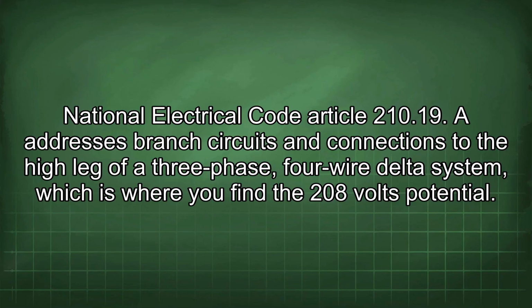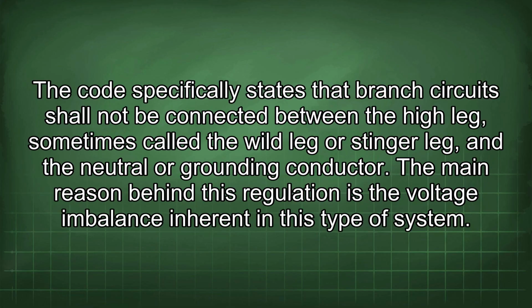National Electrical Code Article 210.19 addresses branch circuits and connections to the high leg of a three-phase, four-wire delta system, which is where you find the 208 volts potential. The code specifically states that branch circuits shall not be connected between the high leg, sometimes called the wild leg or stinger leg, and the neutral or grounding conductor.